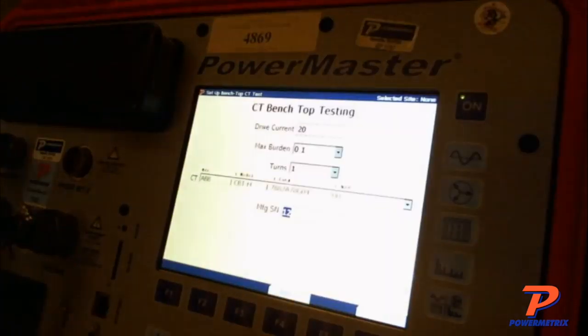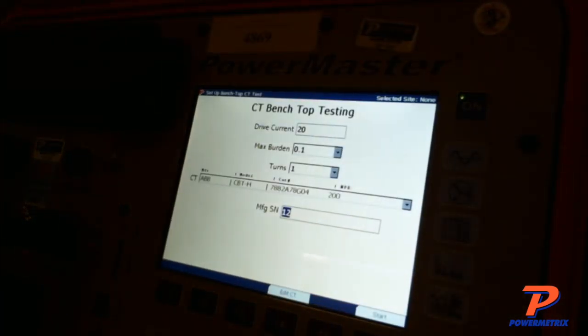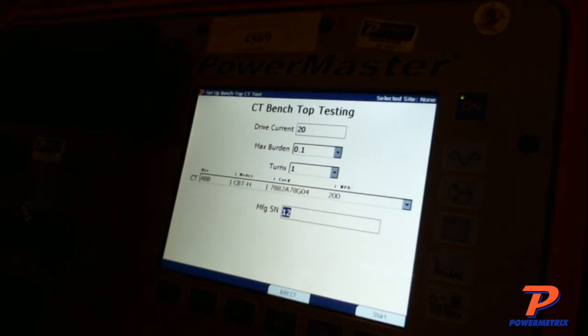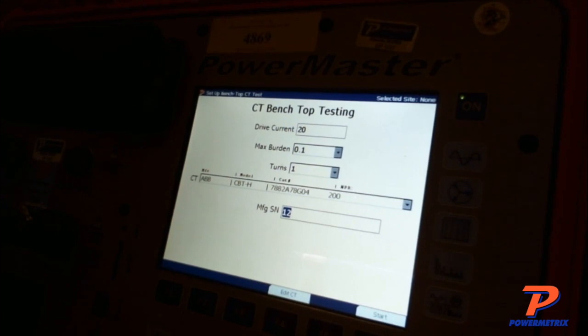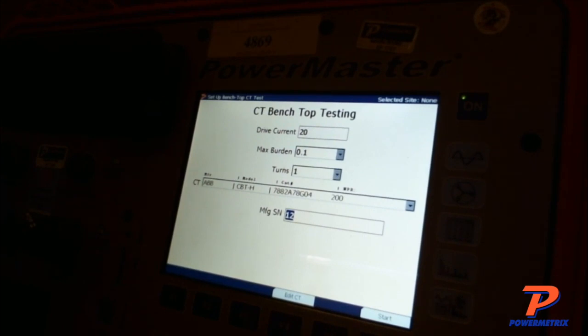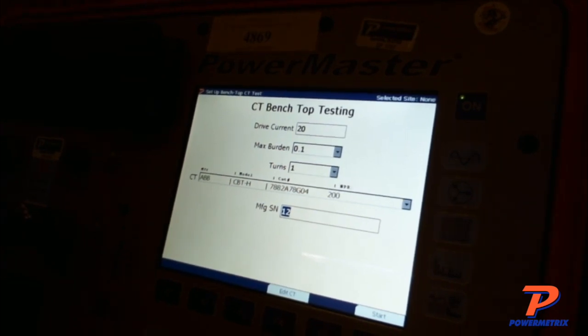And last but not least, when you're in the field, I'm going to have to use my red flexes to pick up my current. But now remember, I'm measuring my primary current with this red flex. My primary current now is two things: it's a summation of what was already there plus my drive cable. So I have to make sure I get both of them in the red flex. When I come in, I want to grab both my drive cable and the primary that's already there. Because if you think about it, what if the amps that are already there aren't enough to test it properly, but they could throw off your test if you didn't include them.